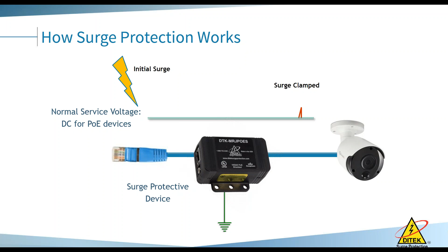You see the surge coming down the line. Without surge protection, it gets right to the camera. When you install one of our devices, in this case an MRJ POE, the surge gets grabbed, shunted to ground, and then self-resets for the next event. It's important to know all our devices self-reset. I can't give you a quantitative number of how many times they'll reset, depending on the environment and the severity and frequency of surges, but up to 20,000 amps, they'll self-reset.